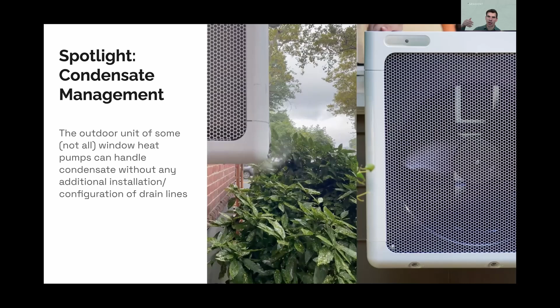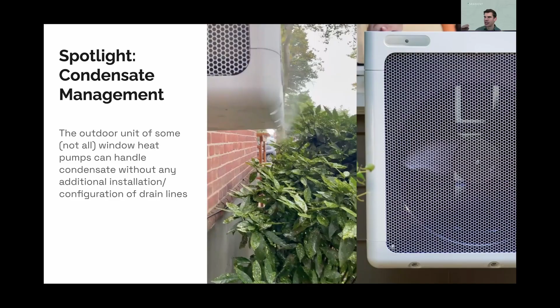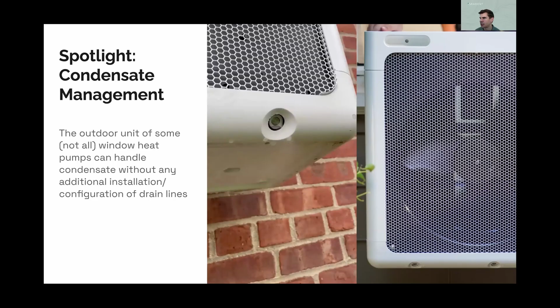Many of these systems have a way to fully atomize the condensate, which is what we're showing in this video here. It basically turns it into mist so that it just blows away. These are freeze-proof systems that operate in the coldest temperatures, and so it means that it is truly plug and play. You do not need any freeze-proof condensate line to be installed. It will just deal with it. The system still includes a standard condensate drain port if, for whatever reason, the customer wants to install a condensate drain system, but generally the system will just handle condensate without any additional install needed.